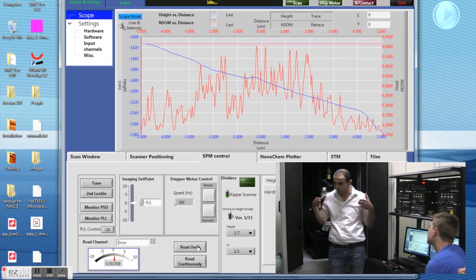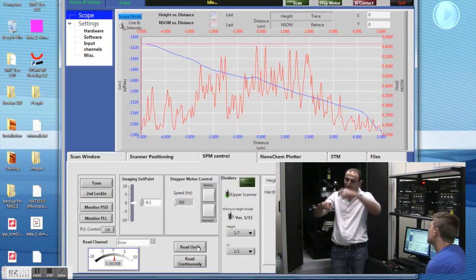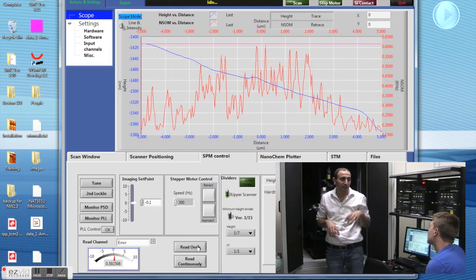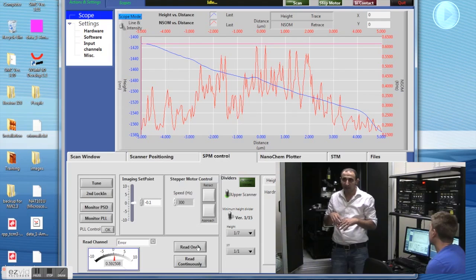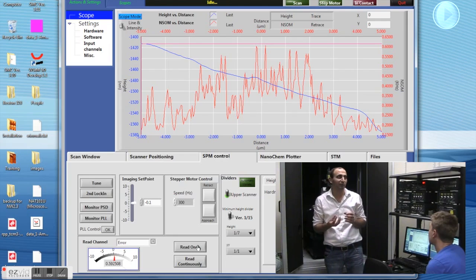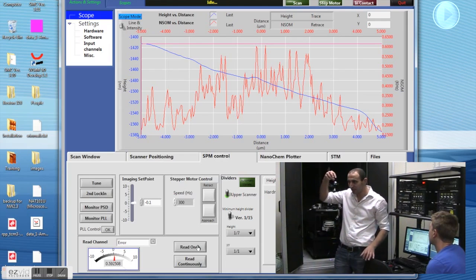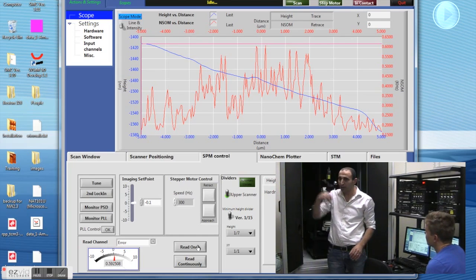It's made of glass, pulled under heat to form a very sharp end, and then it's bent. The bend gives about a few tens of microns between the cantilever and the end of the tip. So when you are focused with a 50x objective on the tip, you don't see any obscuration due to the cantilever. Also the bend angle keeps the tip exposed, so you can easily see the tip touching the surface from the top. You could see this from below in many systems, but only a few systems give you a clear optical access from the top. And that is very important because most of the samples for AFM are opaque.